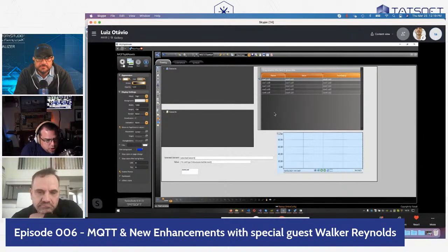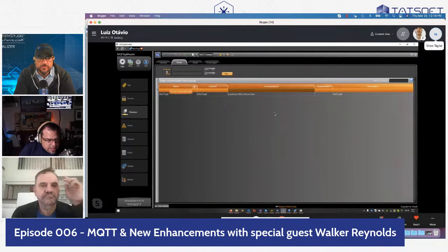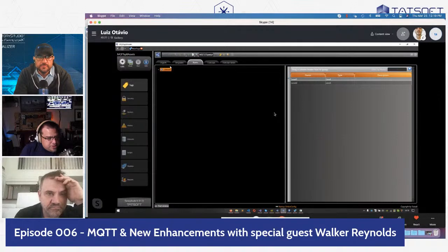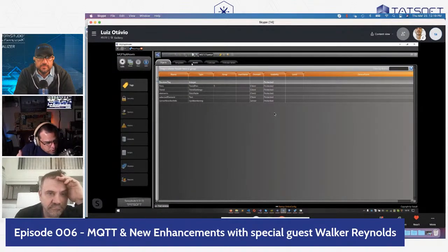If you go to the ORM that is running in the background, when you create a tag, it creates a record inside of a database. There's an integer that's the ID of that tag, there's the name of that tag, and all the other attributes in the table. In most platforms, when you are working with a tag, you are not working with that raw object. What you are working with is an abstraction that points to that raw object, and most of the time that's in some type of tag hierarchy.